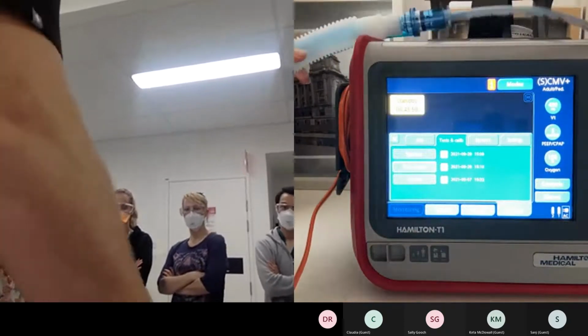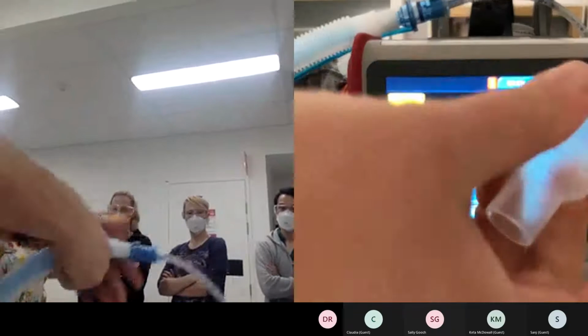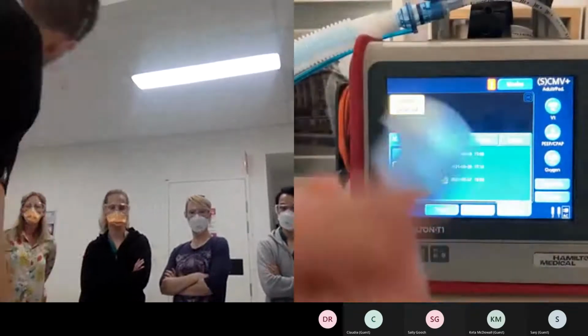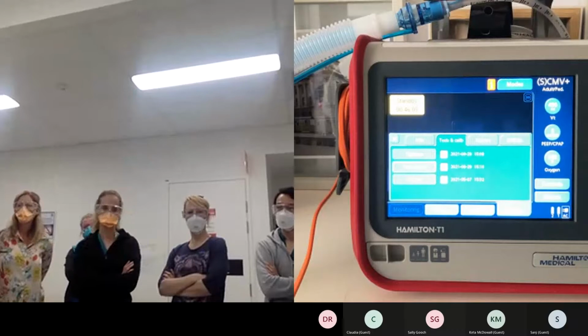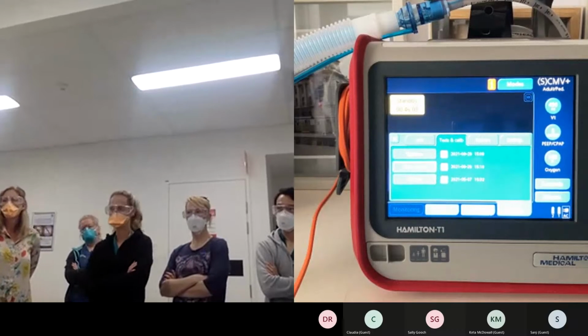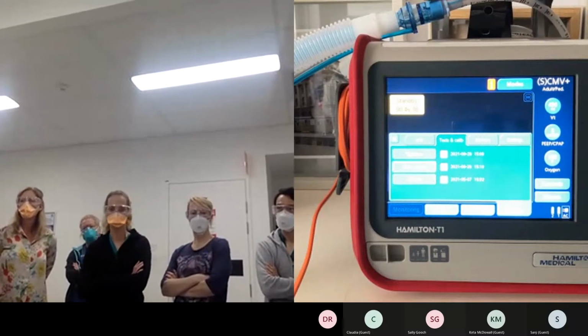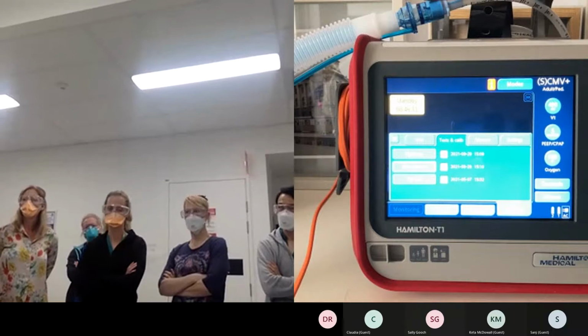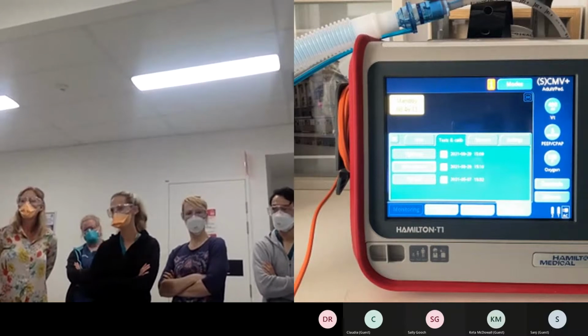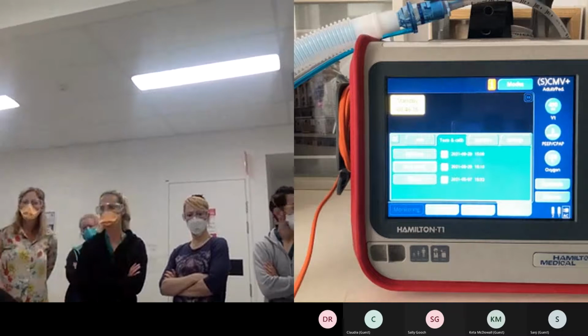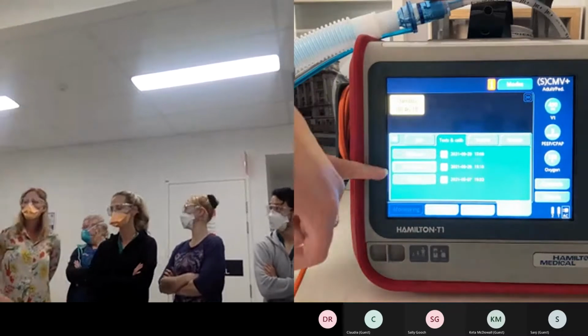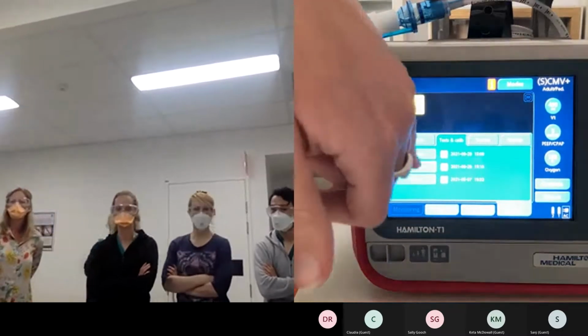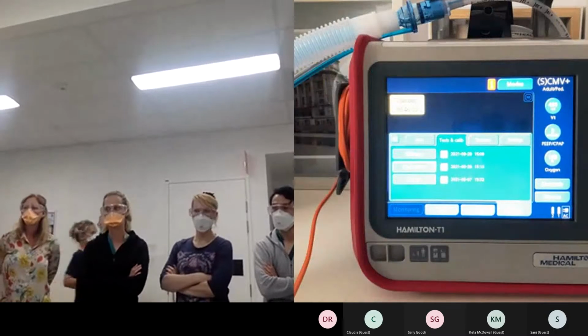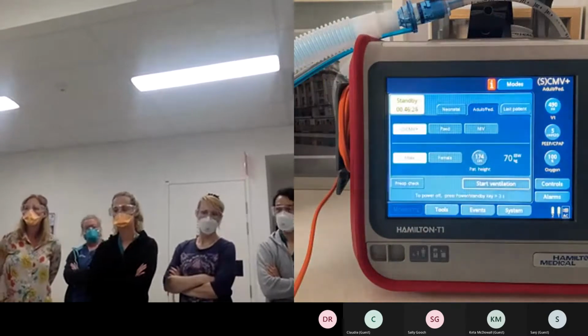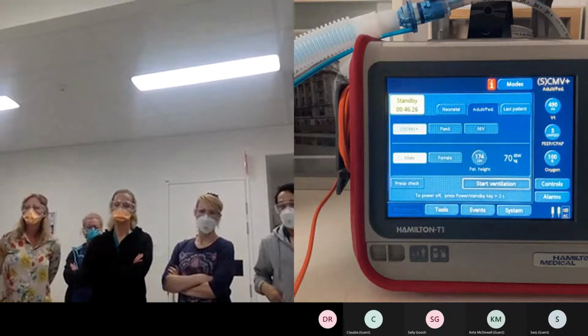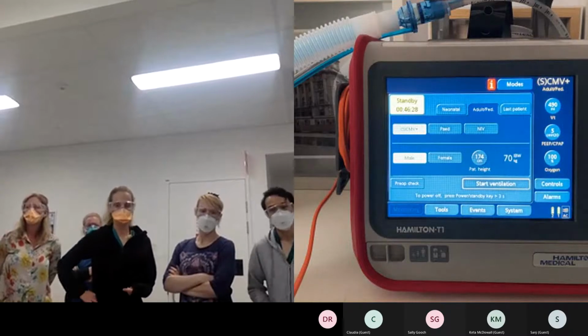With this little connector, in an effort to keep it available for the next shift check, what we teach is that you can pull your line off, loop it through, and it's there for the next shift to use. Okay. If you don't pass that flow sensor check, but you know that you've turned it at the right time, just come back and check your expiratory valve, pull it out, reseat it, and pop it back in.